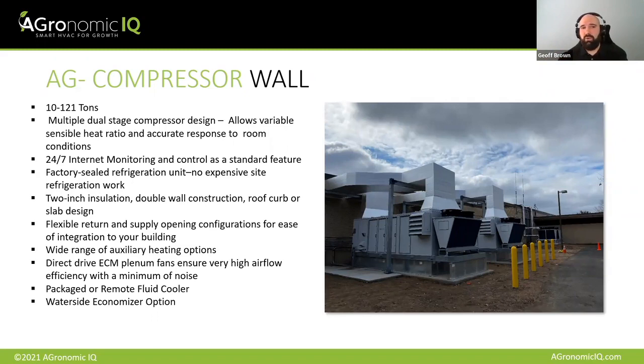So outdoor equipment from 10 to 121 tons. So small rooms to large, we would always recommend having multiple pieces of equipment per room, just for redundancy's sake. You know, a minimum of 2 units per room is generally a good practice. Again, because each of those compressors is a 2-stage compressor. In low speed, they're primarily sensible, that is the air conditioning piece. And in high speed, we add the latent back end, the dehumidification piece.